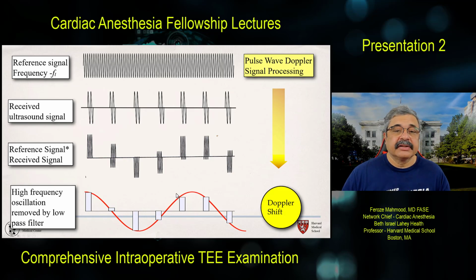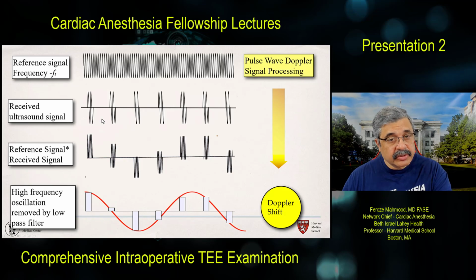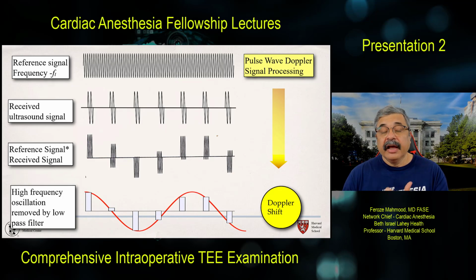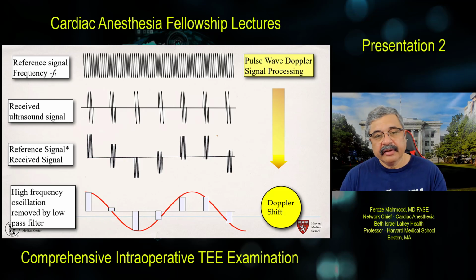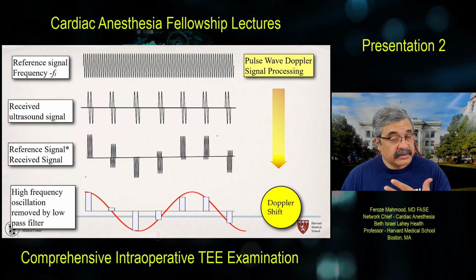The most important thing is that we have to be able to analyze accurately the pulses coming back from that location, because if the go-return time is too long, by the time the second pulse goes to analyze the same RBC, that RBC has moved out of the sample volume. We would not know exactly which direction the RBCs are going, because you will misinterpret and interrogate another RBC in the next cycle that may be closer or farther away from you, and therefore you'd be getting aliasing. So the problem with pulse wave Doppler in the process of signal processing is that it is time gated and therefore susceptible to aliasing.